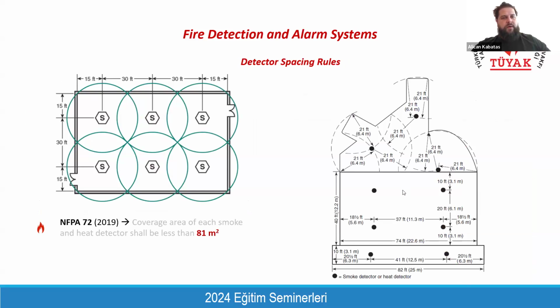This is the spacing rule for the detectors. We have a limitation on the spacing between the detectors, and it should be taken into account because the reflected ceiling plans are prepared by architects on site, and architects are always changing the location of these fire detection devices according to the other installations found on the ceiling. But these spacing rules should be taken into account while preparing reflected ceiling plans. Otherwise, when you send the final design to the consultant, you will get comments about it, and they will ask you to make it code compliant.